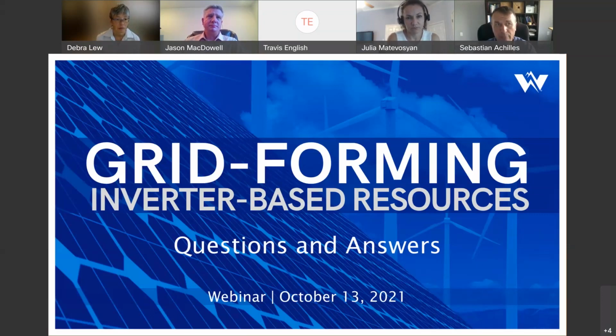On the other hand, what I'm seeing as a consultant looking at system studies is that because we're departing from the power transfer problem toward high IBR penetration, with a mix of loads and several in-feeds, the weighted short circuit ratio is becoming too pessimistic. It's still useful in the sense that you calculate the weighted short circuit ratio for an application and say, if it's less than 1.5, maybe I need to do a more detailed study. But chances are that in this high IBR penetration scenario, 1.5 is going to be perfectly fine. It's just that at the moment we don't have as good a way of anticipating the risk as accurately as we were able to do with the power transfer problem or a power transfer type application.